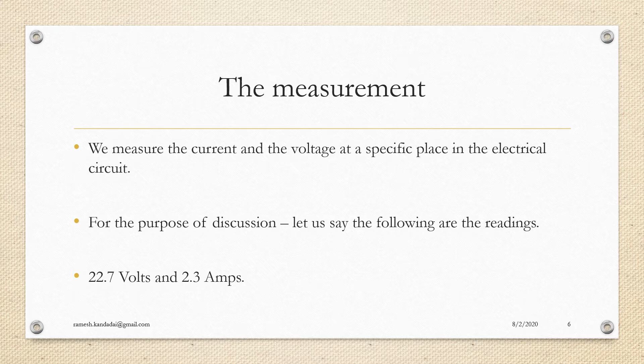Where can the source of trouble be? Each one of these readings, both the voltage and the current, have to be calibrated against a precision supply to verify that when you say 22.7 volts, for example, you mean 22.7 volts, or you will have a range within which the point can be. Even though you say 22.7, it could be any point in a given range.